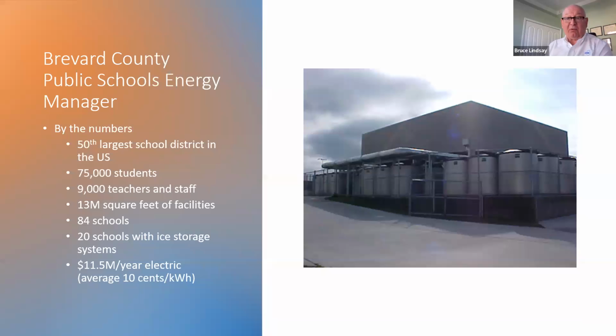Many of you indicated that you're not really familiar with ice storage. This is a central energy plant at one of our high schools. The building in the back holds two 500-ton centrifugal chillers, and those round cylinders sitting there are ice tanks. Those are basically filled with water, and there's a small plastic tubing inside that circulates a water and glycol mixture at 24 degrees Fahrenheit that will freeze the ice, and then we freeze it during the night. And during the day, we reverse the process, and we're able to provide cooling to the entire campus and avoid running the chillers during the day and incurring electric demand charges.